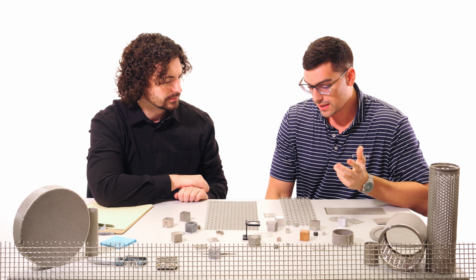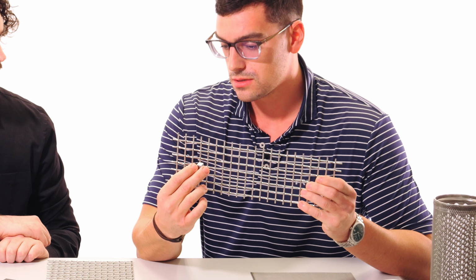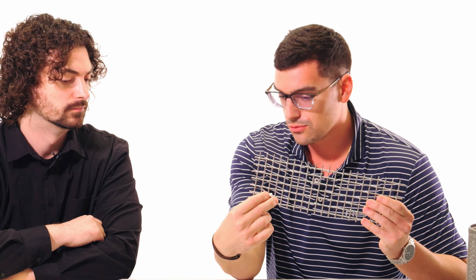And then fouling itself is if, let's say, we have a 40 micron particle and our filter is rated for 40 microns. That would mean that the particle all around has to be the same size as the openings itself, so it ensures that it's either going to be captured by the screen itself or filtered out. If you need an absolute rating of 40 microns for your particle size, you might want to reduce your micron rating of your actual filter itself to maybe 39. So it's an absolute that you know for sure that no 40 micron can get through your screen itself.